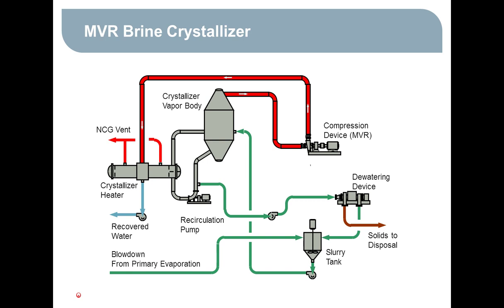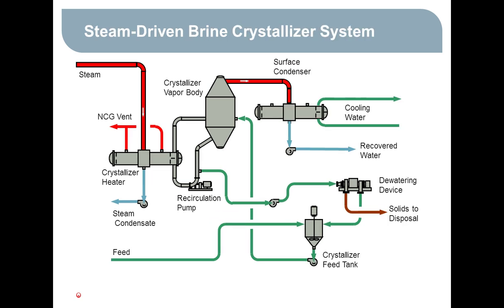You can also drive the crystallizer with steam, external steam. Looks like my diagram fell apart here, so forgive the fact that the pipes aren't quite connected. But external steam can be used to heat the crystallizer heater. And instead of using a compressor, we have a condenser that's cooled by cooling water to take the evaporated water and condense that.